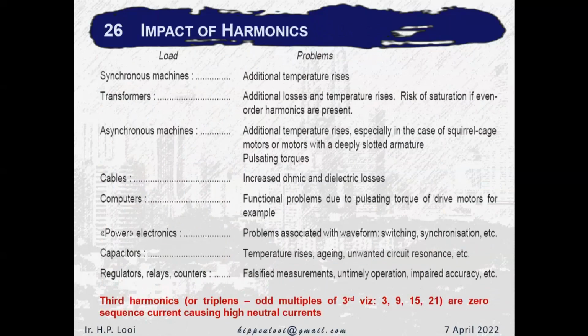Impact of harmonics. You find heating of equipment, temperature rise, cable increase, and especially third harmonics. Third harmonics is what we call a zero sequence phase. It will cause a high neutral current, and I think in wiring standards they recommend that if you assess that you have an issue of third harmonics, then your neutral size must be maybe even full size.